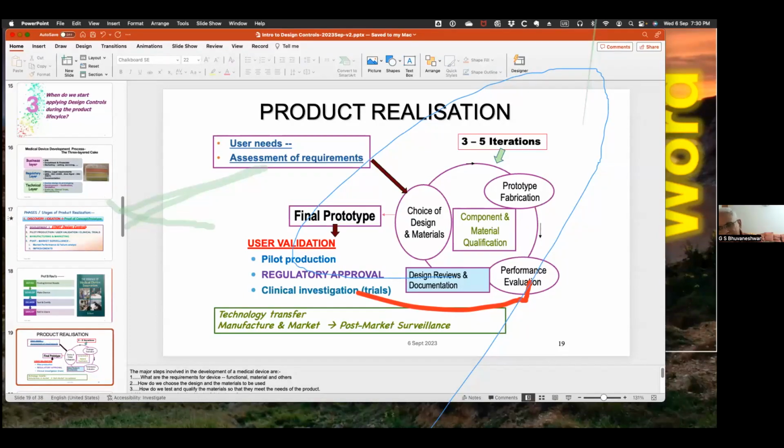But whether, if you're CE certified, they will automatically accept that in the application depends on the specific region or country involved. Most third world countries will accept CE marking today. India does accept many of the US FDA certified devices even today, just like for drugs, they also accept. But I don't think any country will accept a license.